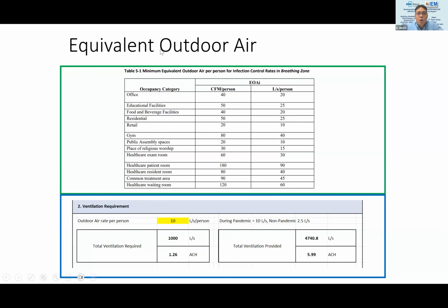This standard uses the term equivalent outdoor air. Like I mentioned, equivalent outdoor air was previously used to flush the building, but now it's used as a benchmark figure for the outdoor air requirement. Previously we all talked about 10 liters per second, now there are different liters per second. But if you use the MVC, you can just key in here. If you want to design for a gym at 40 liters per second, you can key that in. We use this outdoor air rate per person as an equivalent outdoor air, while the MVC uses equivalent ventilation. So these are all interchangeable terms, even before the pandemic.